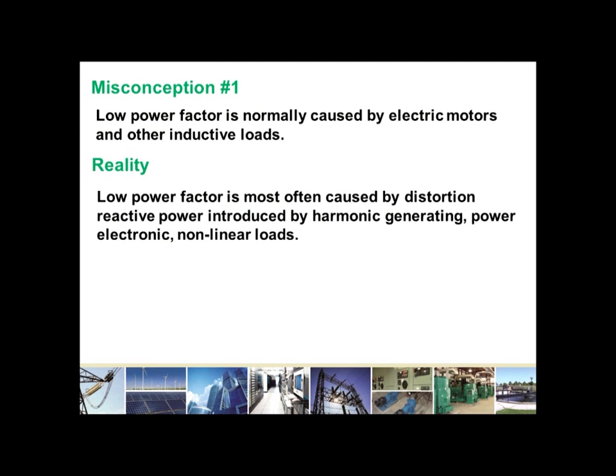So the first misconception on power factor is that low power factor is normally caused by electric motors and other inductive loads. Whereas in reality, low power factor is most often caused by distortion, reactive power introduced by harmonic generating power electronic nonlinear loads.